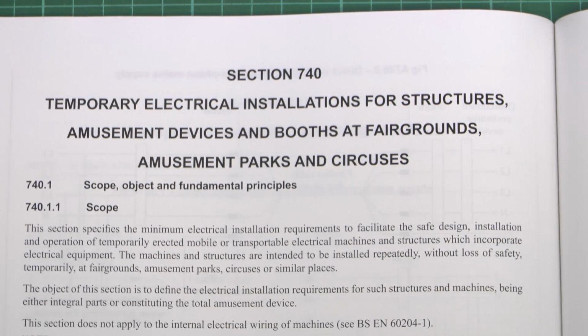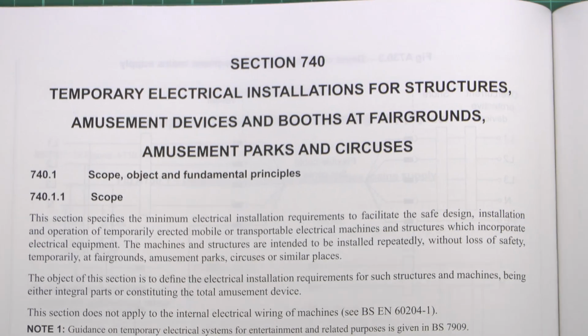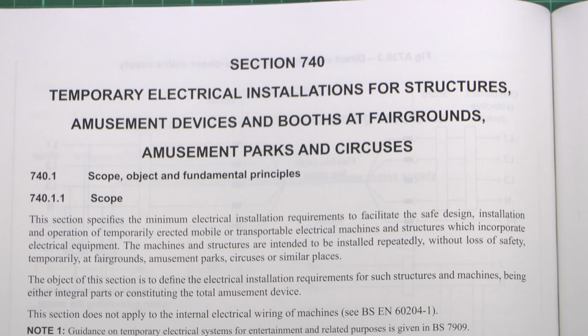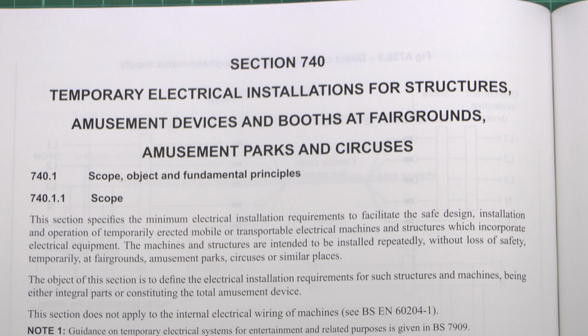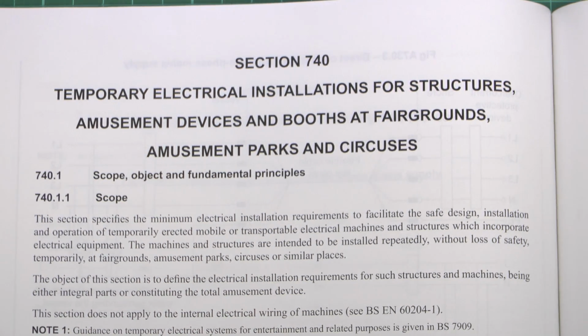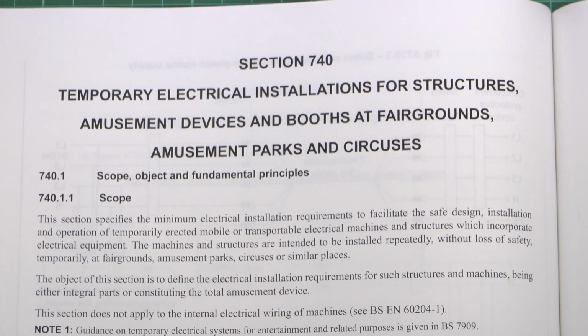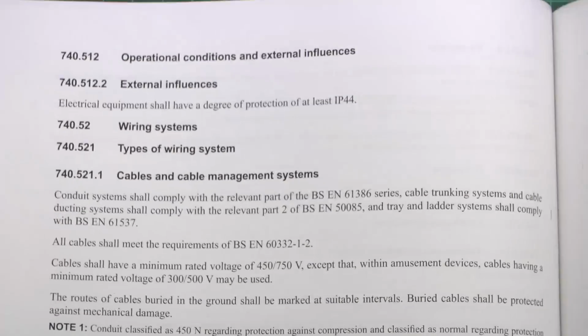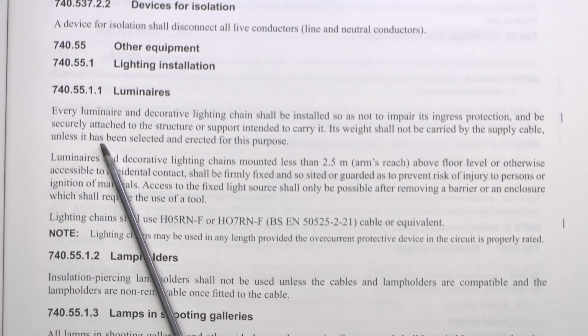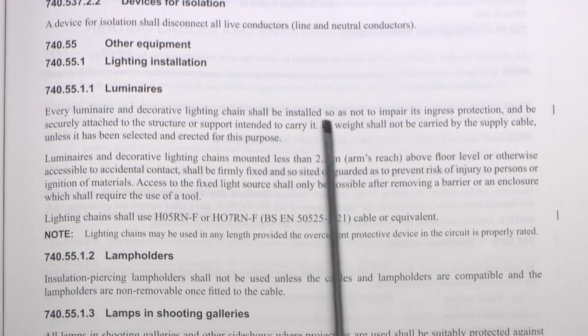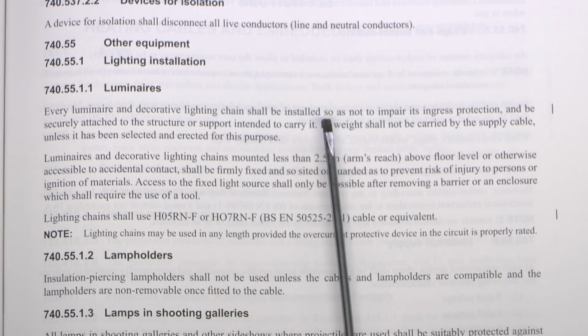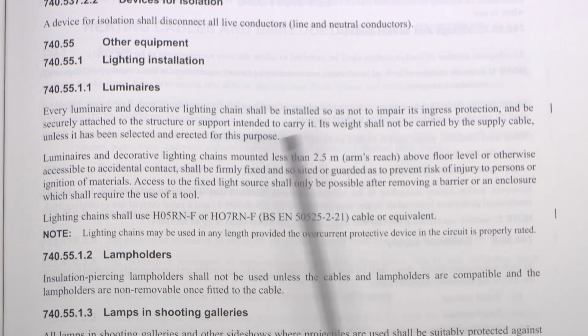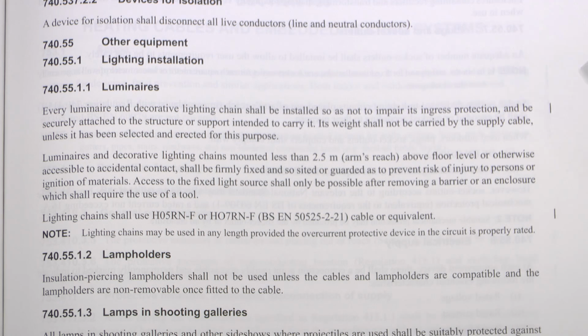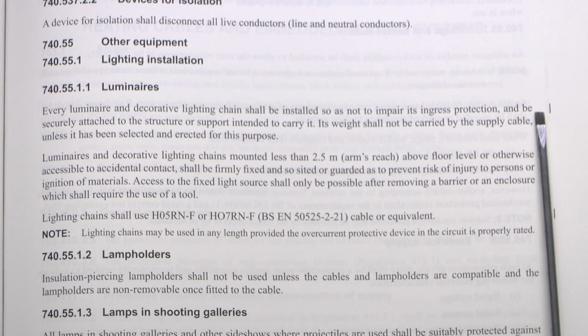Now section 740, which is for temporary electrical installations for amusement devices, fairgrounds, circuses and similar, there's only really two changes here. First of which is 740.55.1.1. That's the one here about luminaires. And all that's happened here, there used to be a phrase here which stated shall have a suitable IP rating. That has been deleted, and the rest of it again is pretty much the same as before, and that's what the mark there actually indicates.